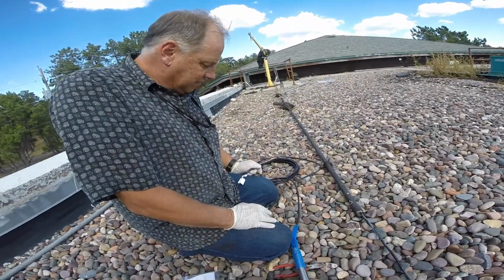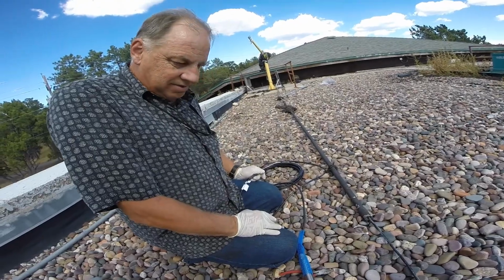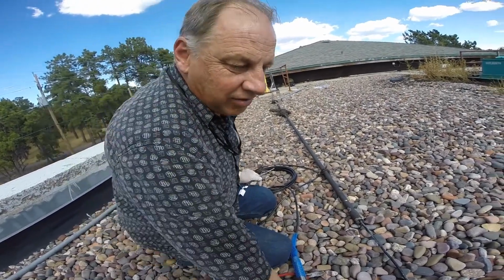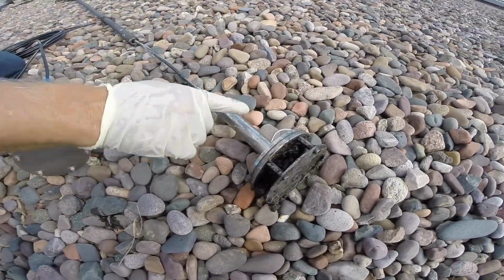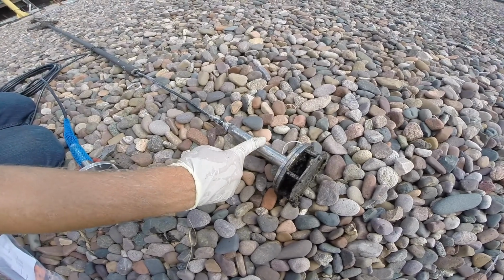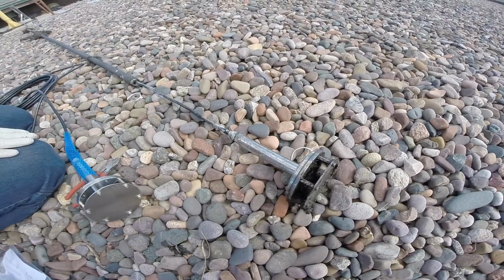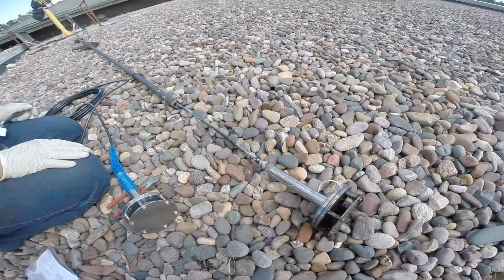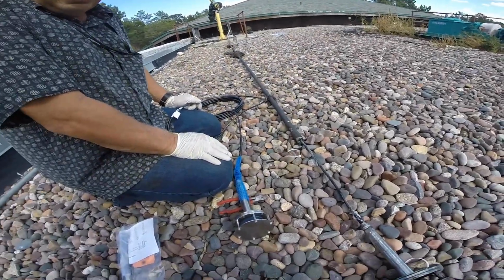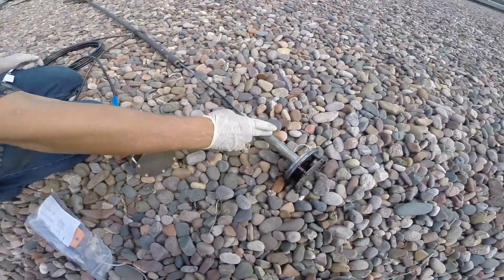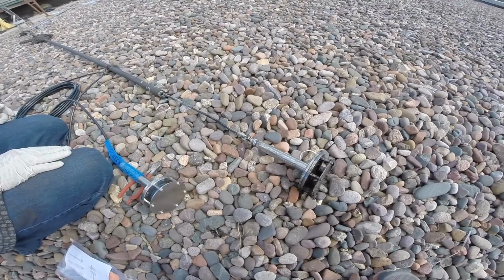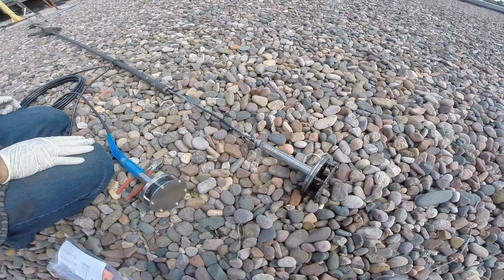So now there's water on the other side of the diaphragm causing it to read incorrectly. That extra moisture getting into the tube adds weight, so the weight of the water against the weight of that little column of water on this side makes it look like it's not as deep. That makes the differential pressure lower. Over time, water builds up in the tube, and eventually the pressure transducer won't read any difference at all.